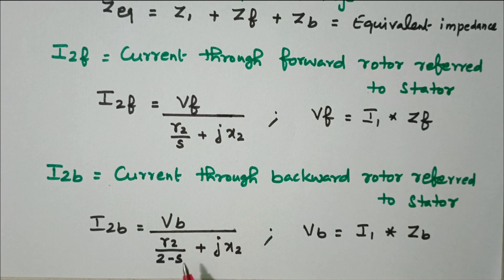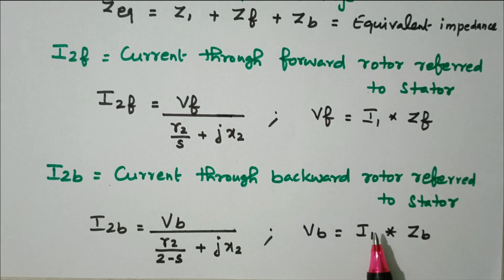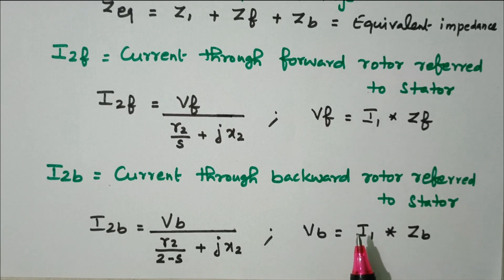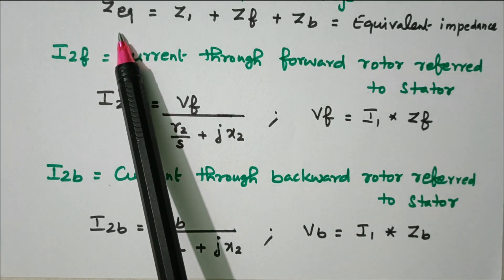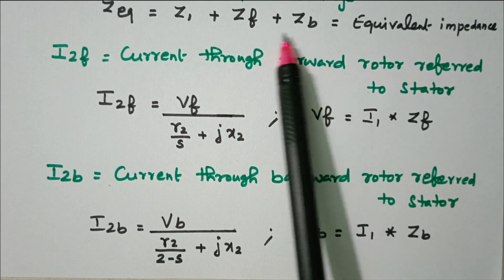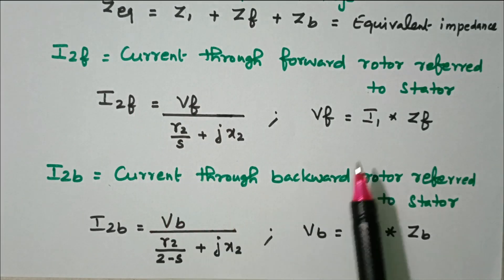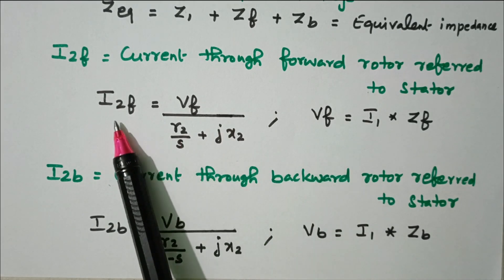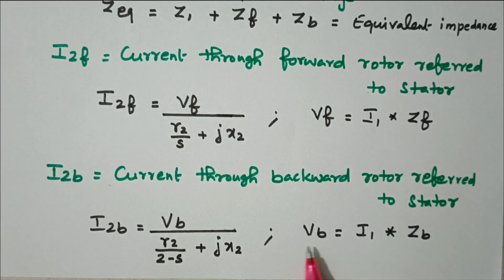So s refers to forward rotation and 2 minus s refers to backward rotation. Starting from the stator and moving to the two imaginary rotors — forward and backward — we calculated zf and zb. From these we get the total equivalent impedance z_eq equals z1 plus zf plus zb, then forward voltage and current, and reverse voltage and current.